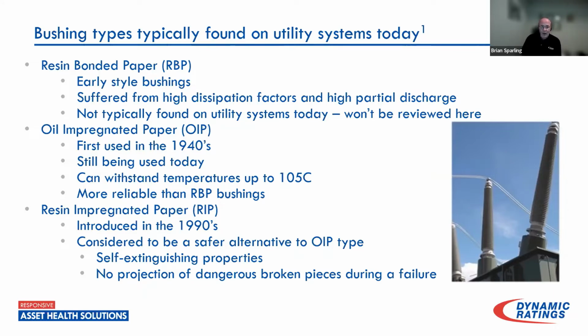OIP stands for oil impregnated paper, and this refers to the insulation system inside the bushings that makes up the condenser. They first came out in the 1940s. It's the predominant bushing that's in use today. People understand the technology, and they can sustain a lot of, I use the term abuse, but use, and they have proven over time to be much more reliable than RBP bushings.